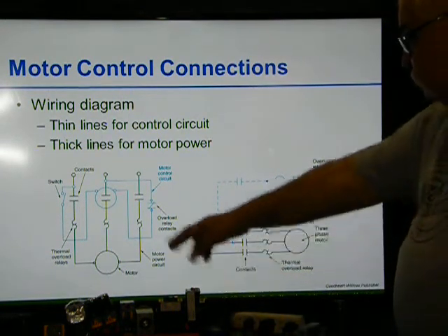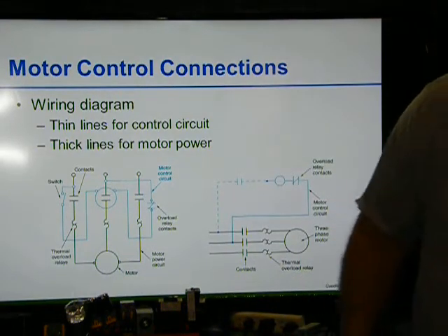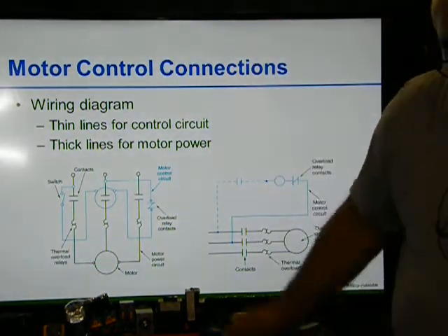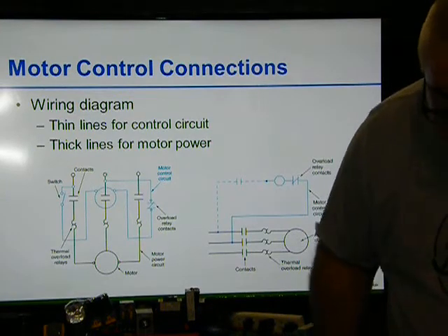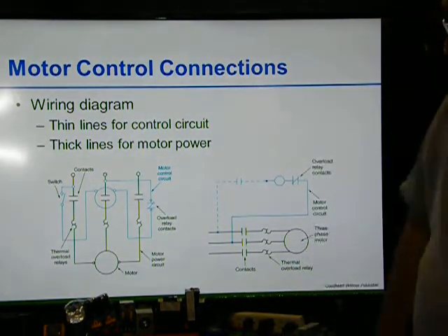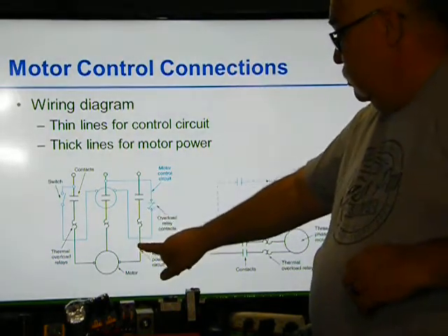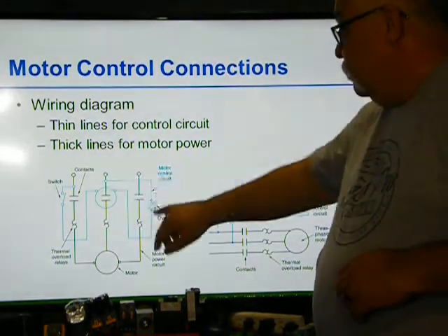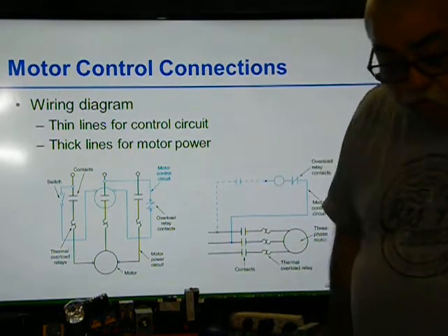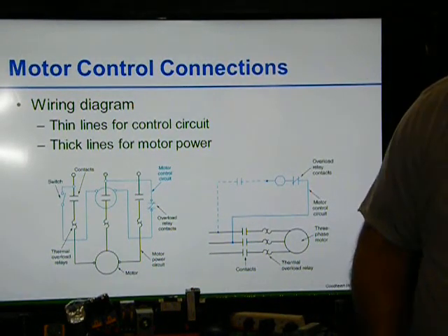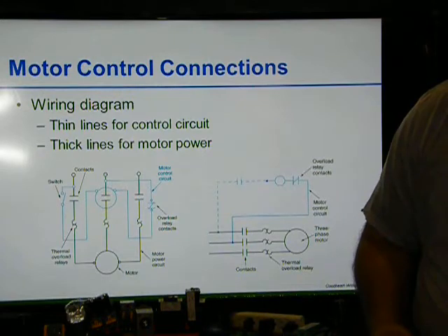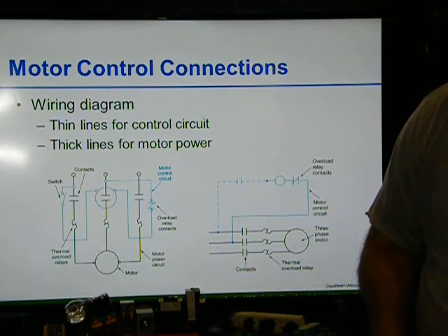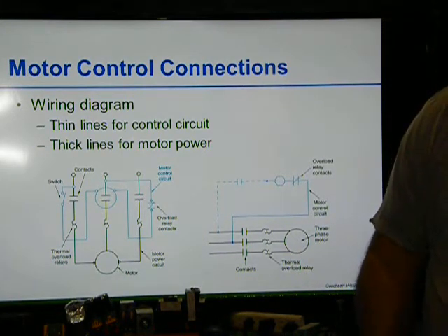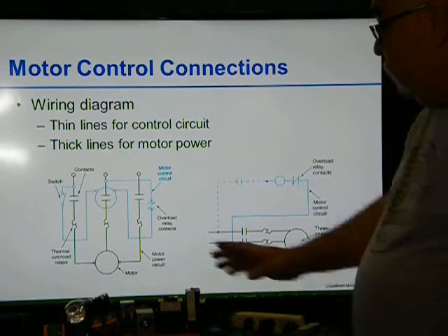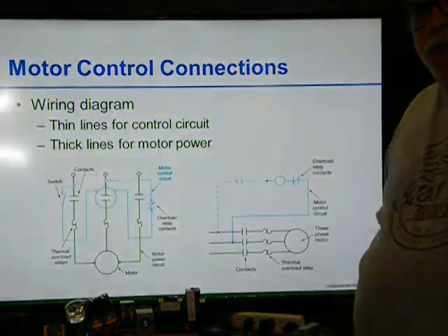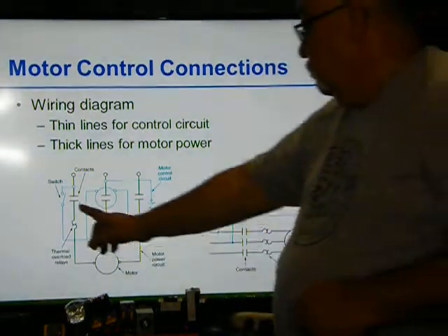Okay, this is the elementary drawing, and that is a wiring diagram. And then this is the elementary drawing of a 2-wire. Always remember, your darker lines would be your power for the motor, and your thin lines would be for the control circuit. Control circuits are always specific. So the control diagram shows the circuit in the off condition. Anytime you look at the drawing, it's always in the off position.